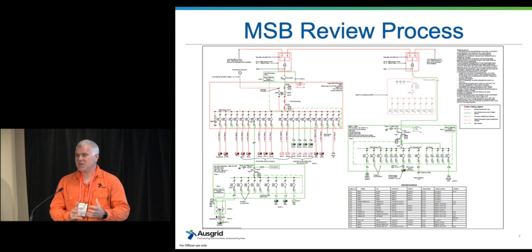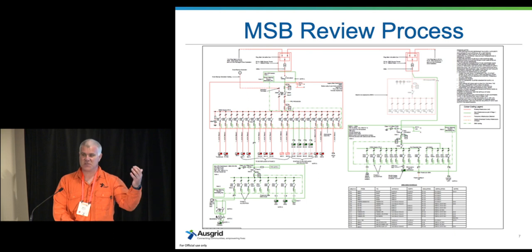As much information as you can give us is the only information we're able to provide a response on. Often we get to site and we've been given about 10% of what is actually there. That makes it pretty hard for us to continue with an energisation if we find issues with another part of the installation we were never made aware of. PV downstream of generators, you can't have that. It's supposed to be connected upstream.